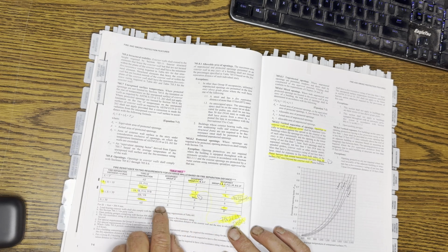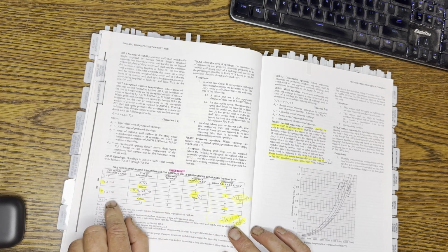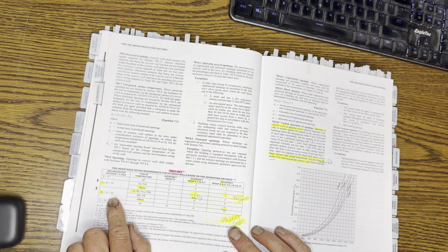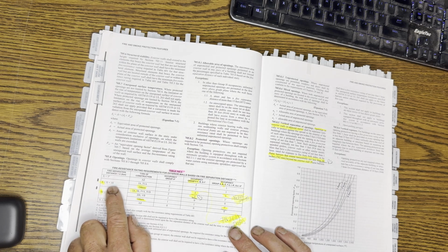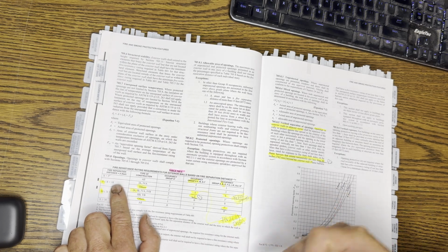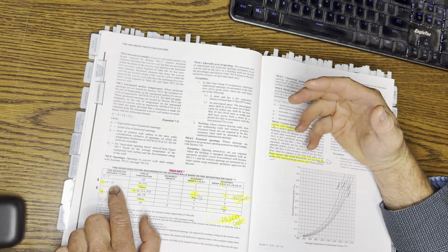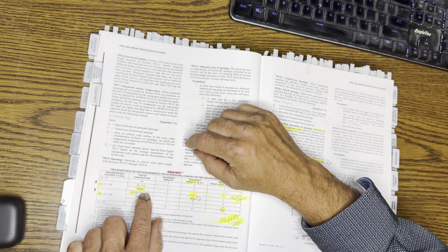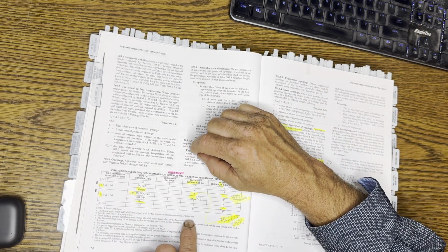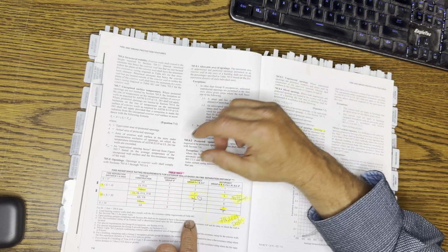What I want to emphasize is you're more than 10 feet away. You got to double these numbers on this size. So 60 feet's a magic number. 20 feet's a magic number. If you are 20 feet away from another structure, you need no exterior fire rating on your exterior walls.